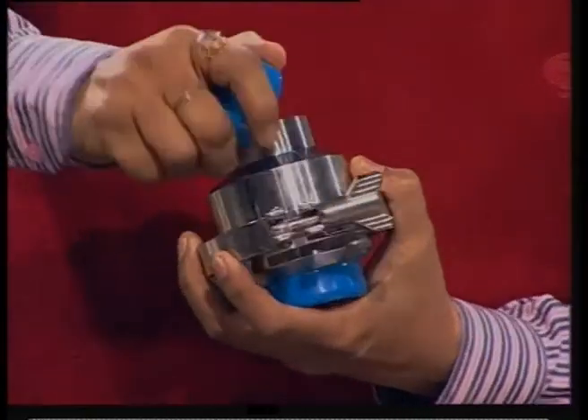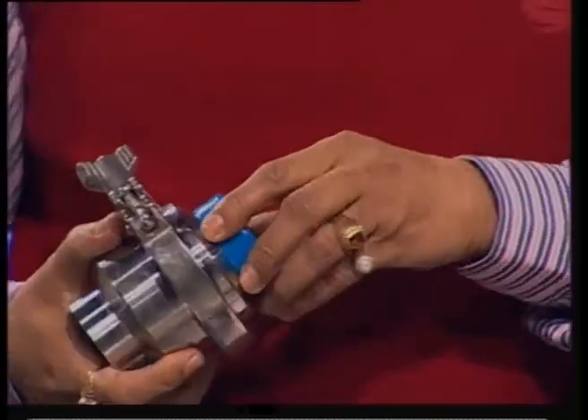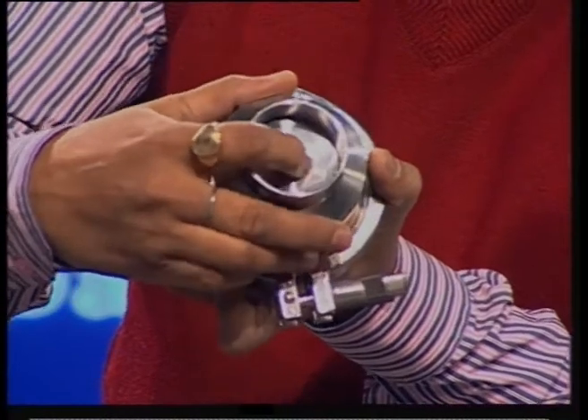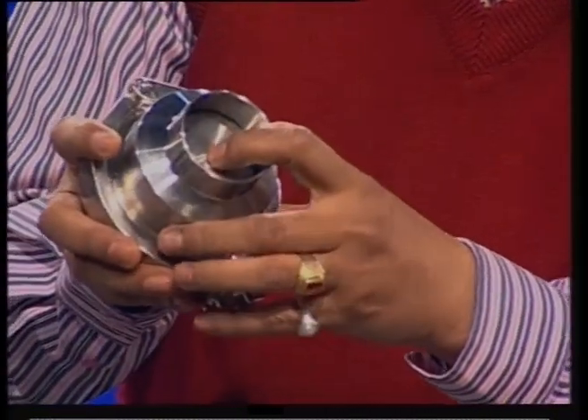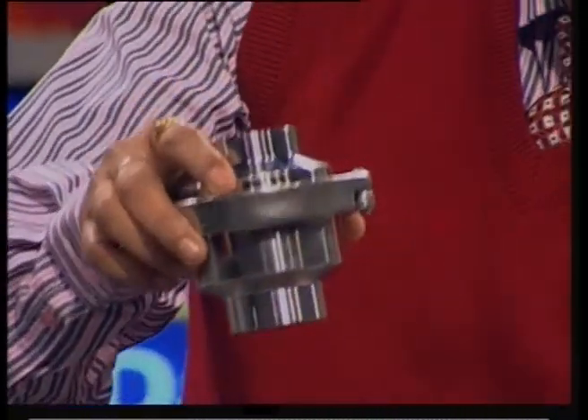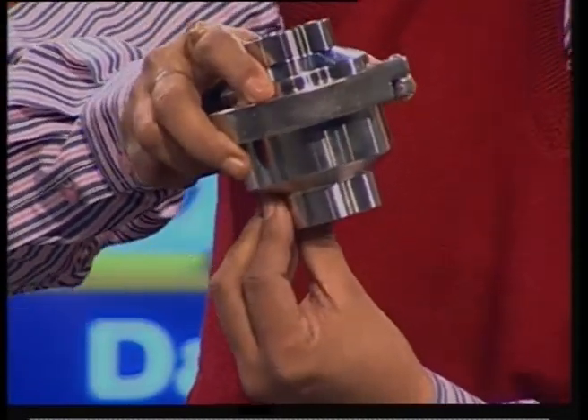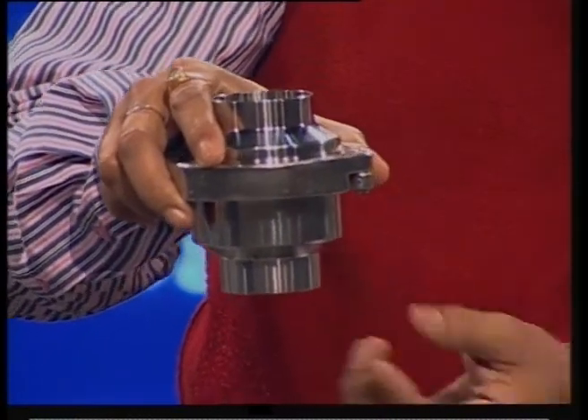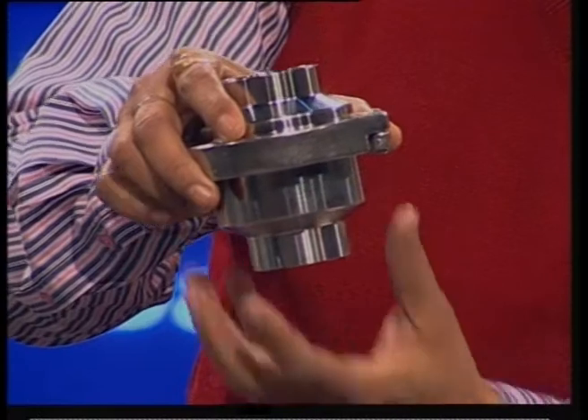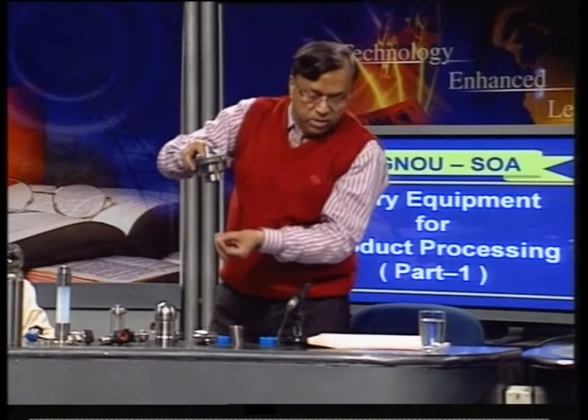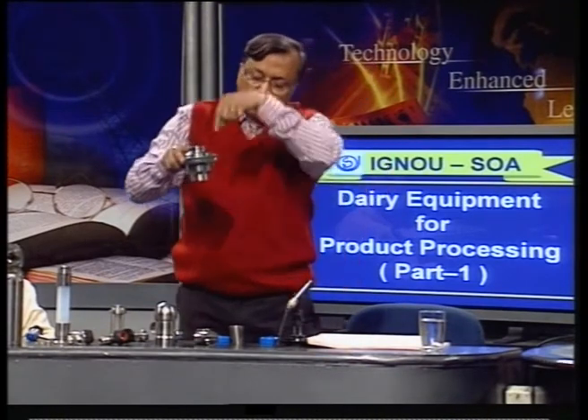The check valve is a one-way valve, in simple language. If you see at the top, there is a spring-loaded mechanism. When there is sufficient pressure — from the pump — the liquid comes out and goes to the next system. If the pump stops, the product in the line, maybe 10 to 20 feet, will stop and will not come back. It only allows the product to go forward, not to return.